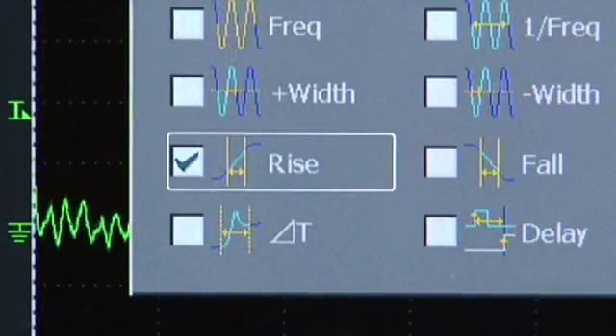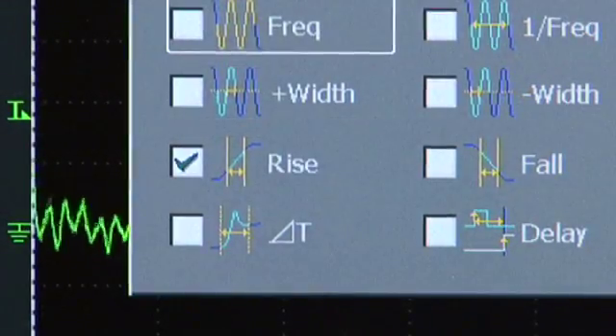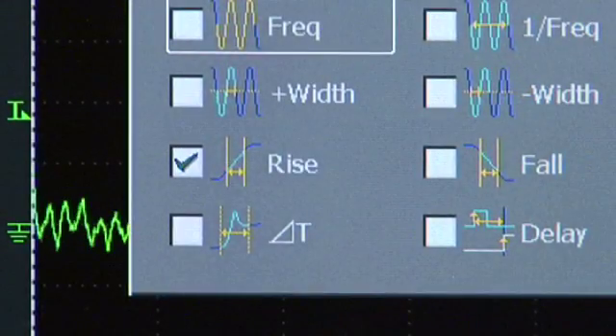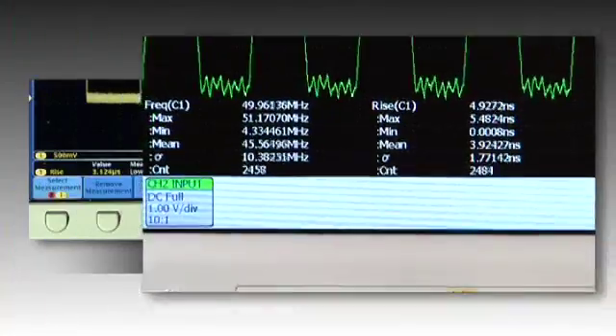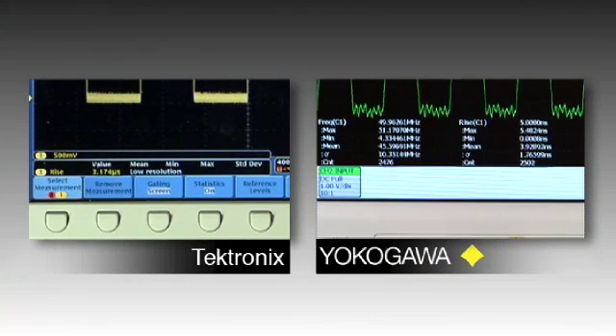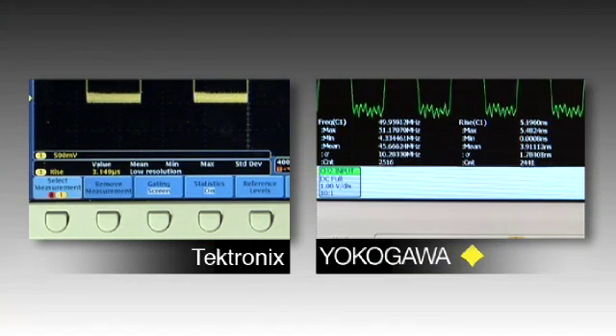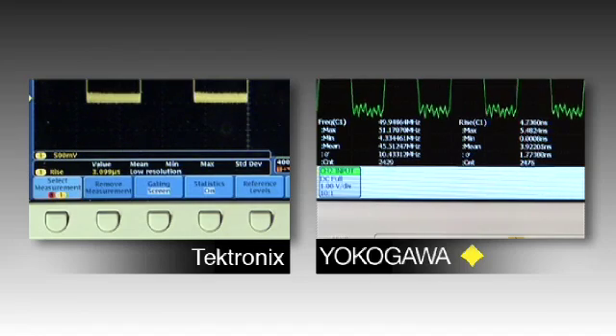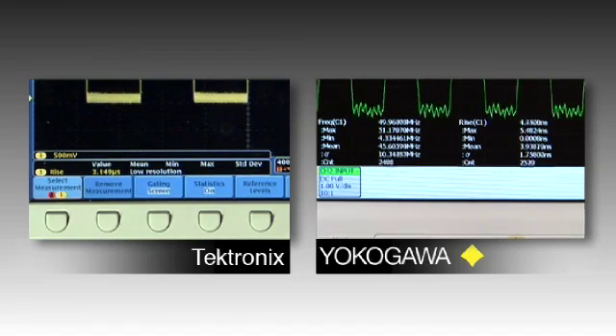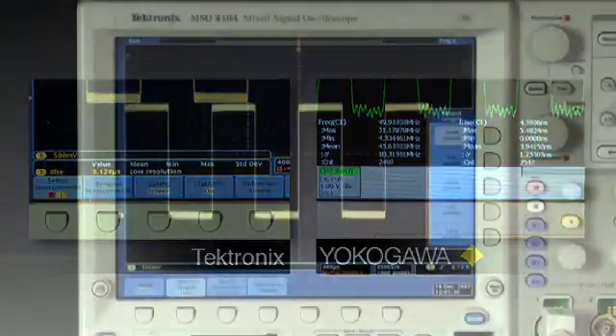Let's select a rise time measurement on both instruments. With both instruments set to the shortest record length, the DL9000 can measure max, min, mean, and standard deviation of rise time over ten times faster than the Tektronix.